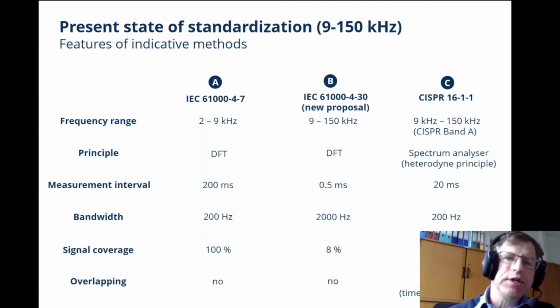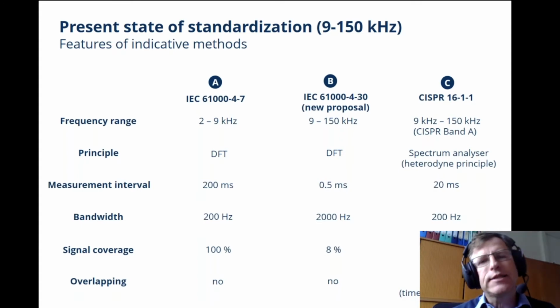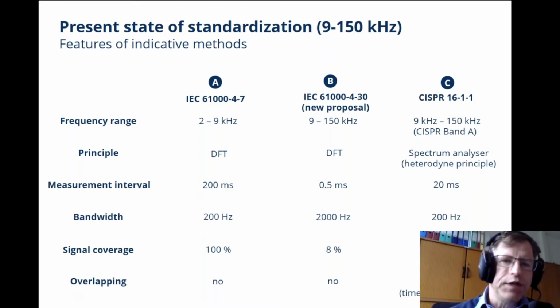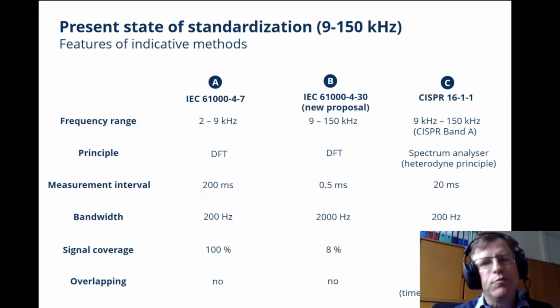There is another method, much less computationally burdensome, proposed in 61000-4-30, which I call a new proposal, also based on DFT. You only take 0.5 millisecond windows, giving a 2 kilohertz resolution of the spectrum. However, since you only take 32 times 0.5 milliseconds within 200 milliseconds, the signal coverage is only 8%. There's certainly no overlapping, rather a gapping.